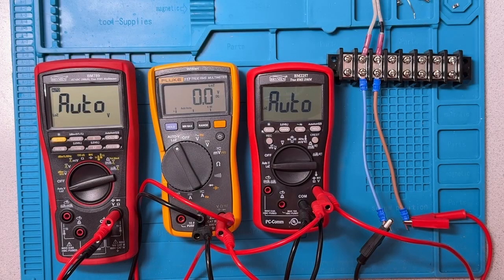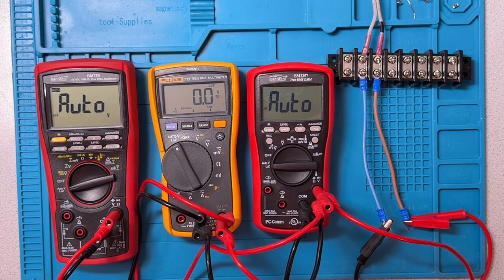So now let's look at the 3 meters in the low Z mode. And so that provides a low impedance pathway in the meter to try to eliminate the ghost voltages. So right now they're all showing either auto in the case of the 2 Brymens or 0 in terms of the Fluke. And the power is off, and so that's more or less what we would expect. So there's no voltage there at the moment.